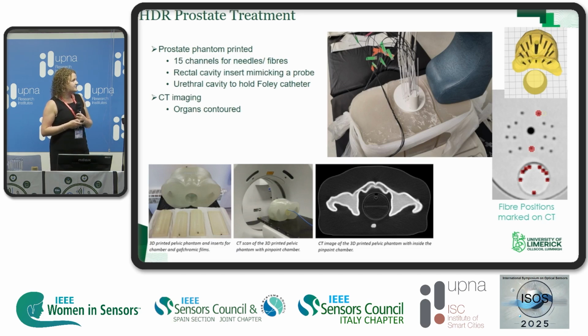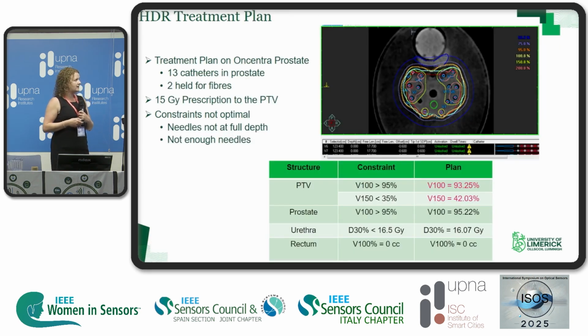Looking then at the prostate treatment, we have a 3D printed anthropomorphic phantom where we're able to place inserts and optimize the patient anatomy and the sensor positions for it. We developed a full treatment plan for the phantom and looked at how our dose rates compared to the treatment plan. So what we have here is 13 catheters placed into the prostate and 2 additional ones that hold the fibers.